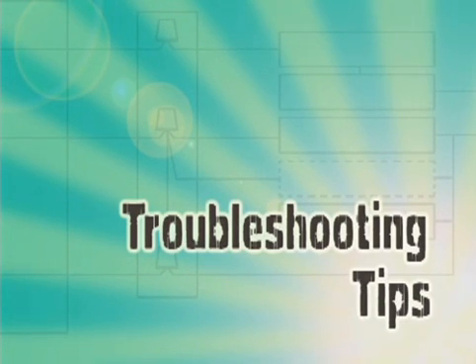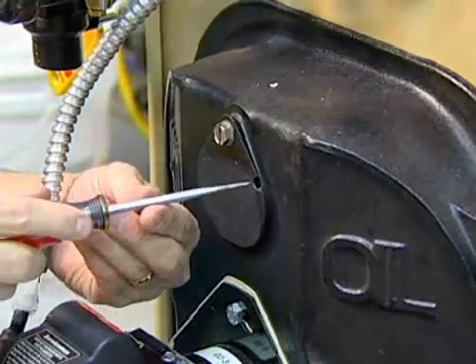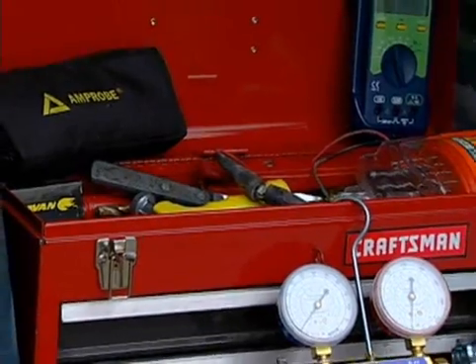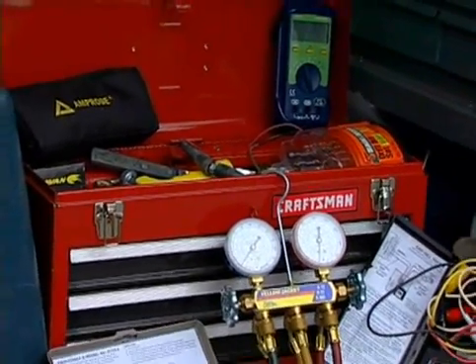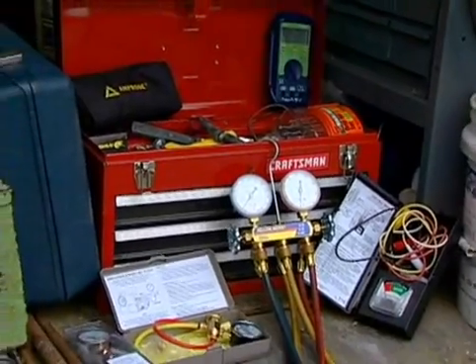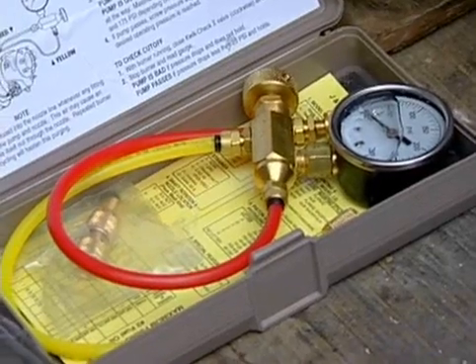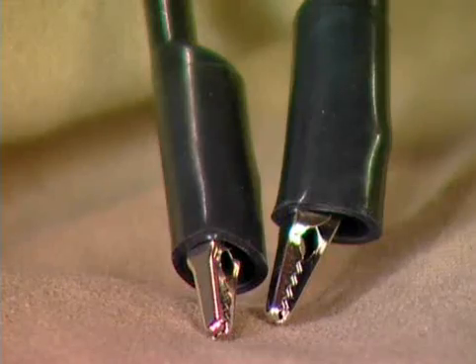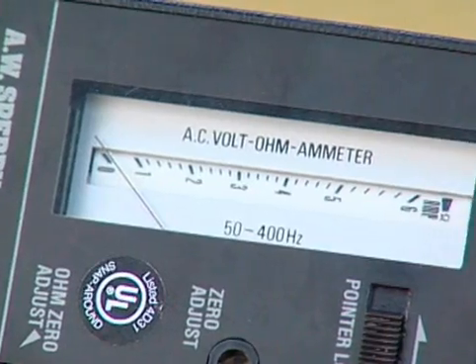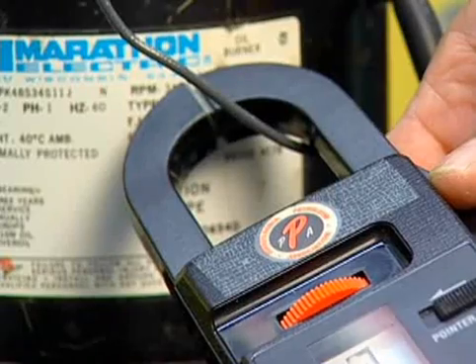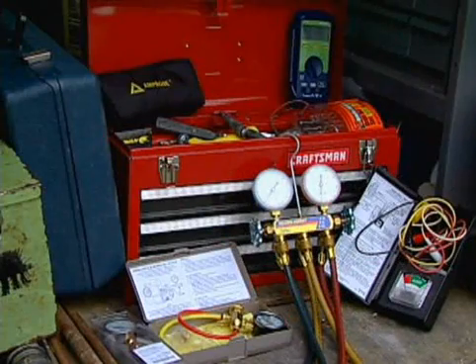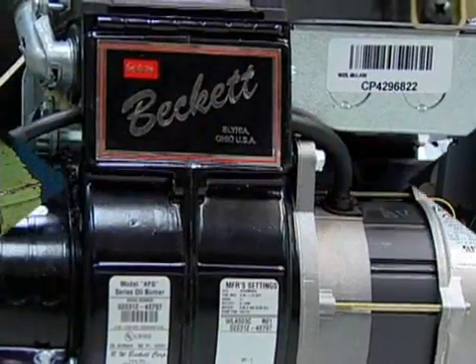Professional service technicians understand that accurate troubleshooting requires the proper tools. In addition to a complete set of hand tools, oil heat service technicians should carry and use appropriate test equipment, including an efficiency kit, vacuum and pressure gauges, insulated jumper wires, a voltmeter, an ohm meter, and an amp probe. The proper use of this equipment simplifies troubleshooting and eliminates guesswork.